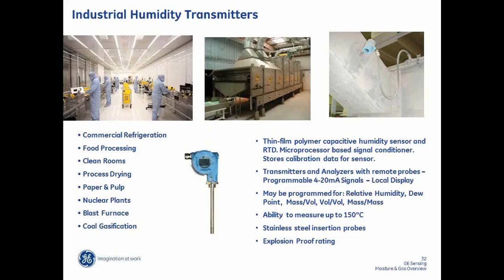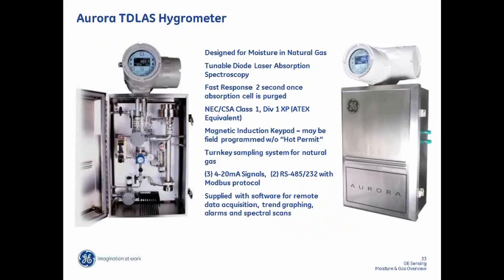The next technology is our TDLAS, which is the laser. And our laser has been primarily designed for moisture in natural gas. However, we've applied it to a number of different applications, including furnaces and now a nuclear application where it's measuring CO2 in a containment. So these are configured in a complete sampling system, or we now have also a benchtop version of this, and they carry the explosion-proof certifications. They'll put out 4 to 20 milliamp as well as the digital interface, serial interface with Modbus.